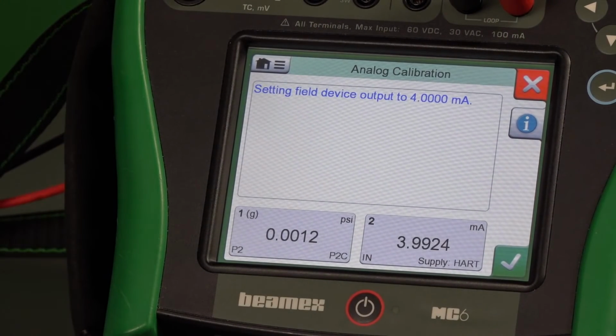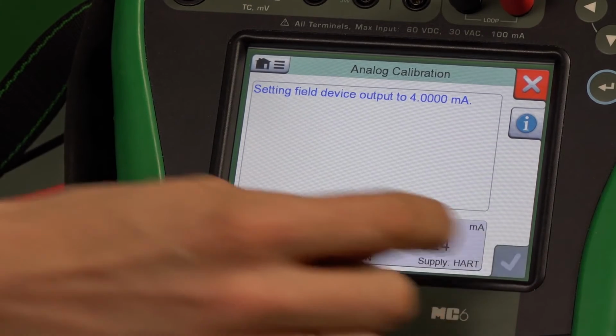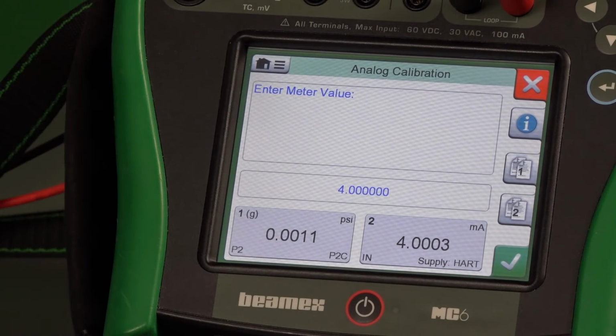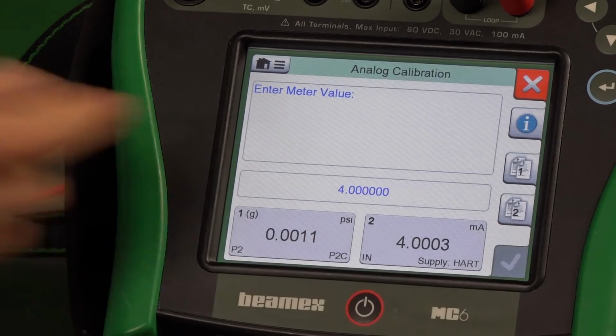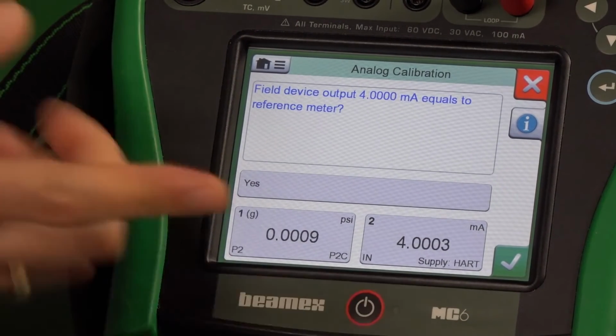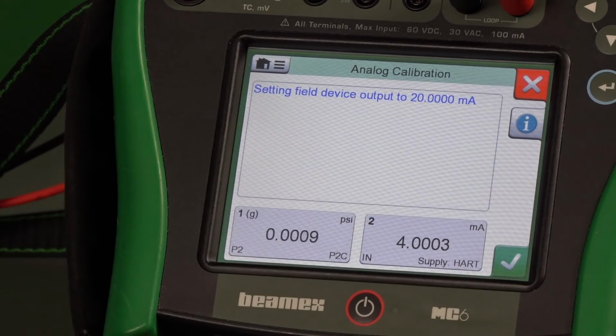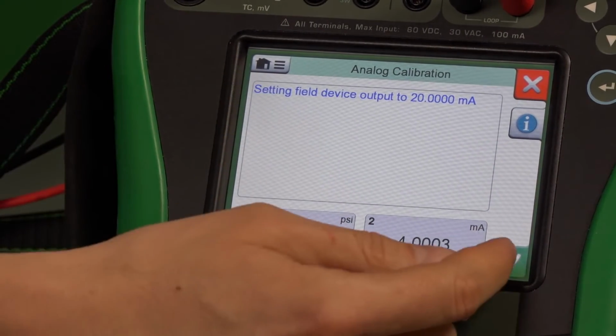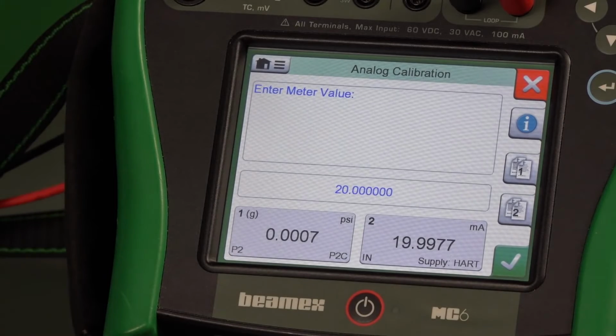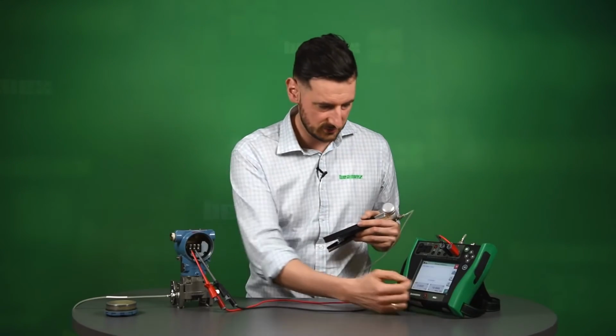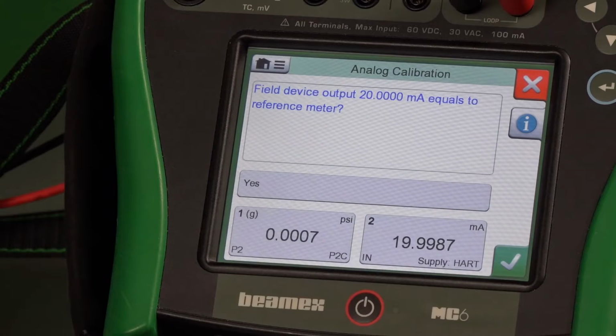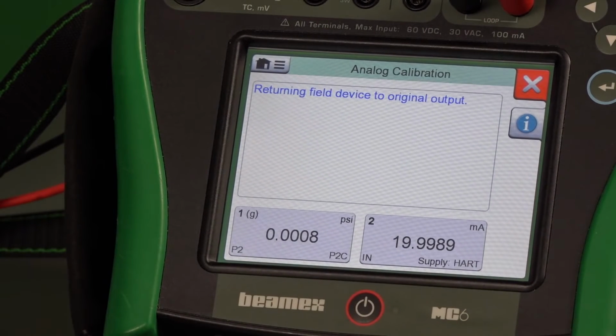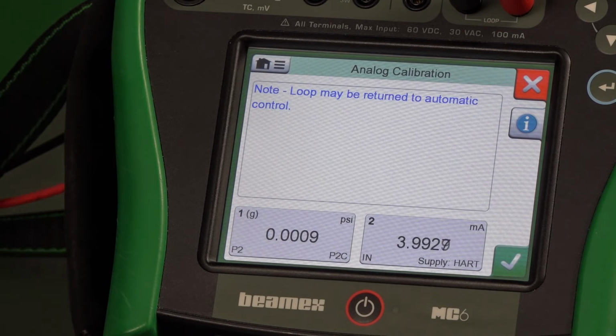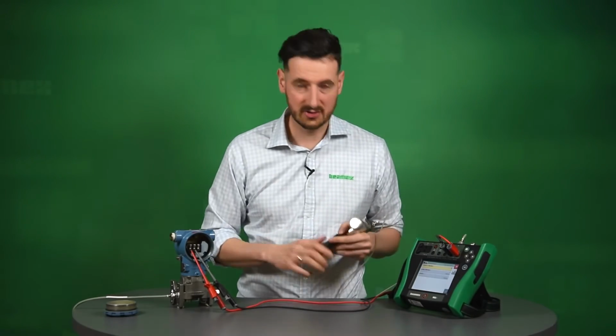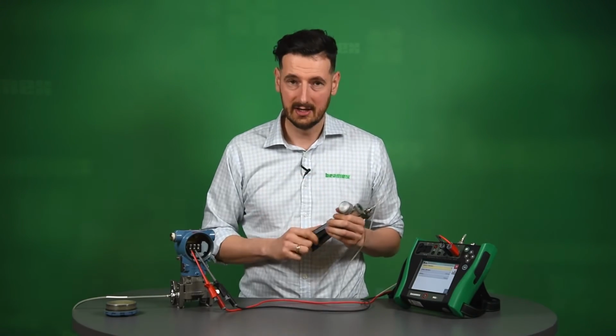It's actually telling us that it's going to set up the transmitter to 4 milliamps. You just click OK. You enter the meter value. It's 4 milliamps. You click OK again. It's asking you whether that's actually 4 milliamps. It is. So you're just basically following the instructions. The instruction right now is saying that it's going to do 20 milliamps. You follow the instructions. It's setting the device to 20 milliamps. You click OK. Yes, it is more or less 20 milliamps. We're happy with that. So it's returning right now back to what it was. So it's fine. Analog calibration, analog trim is done.